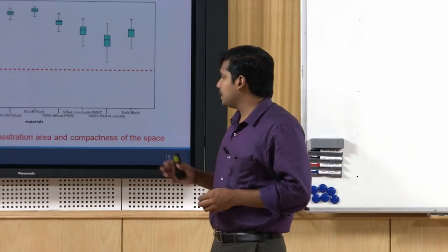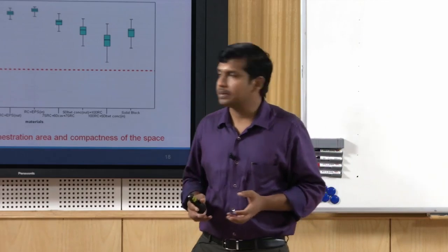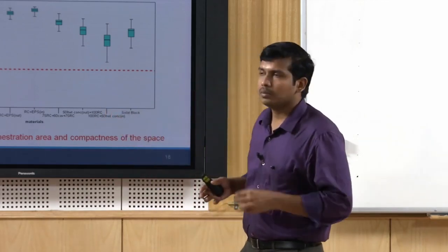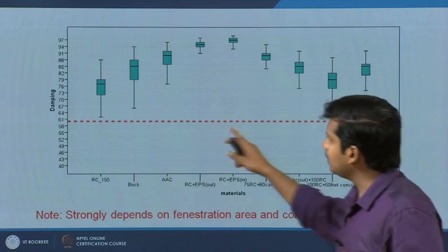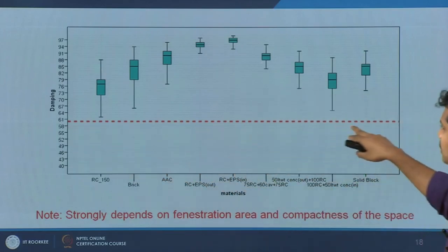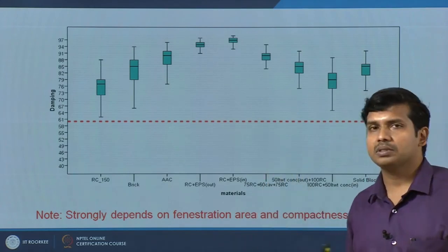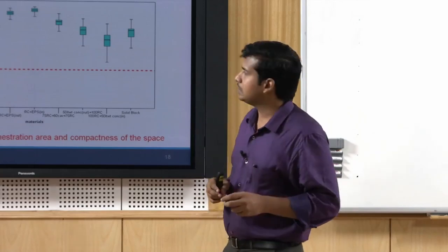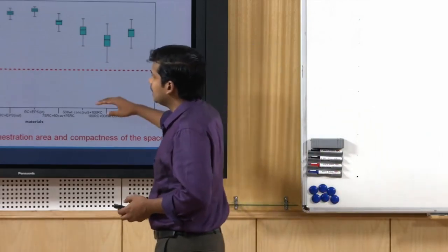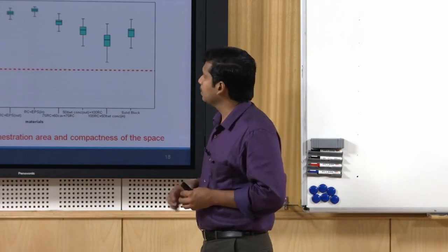Thermal damping strongly depends on the fenestration area and the compactness of the space. Looking at what the national code specifies — for a hot and dry climate where we did the assessment — the minimum required thermal damping was 60 percent. Below this the wall is not compliant to the national building code.